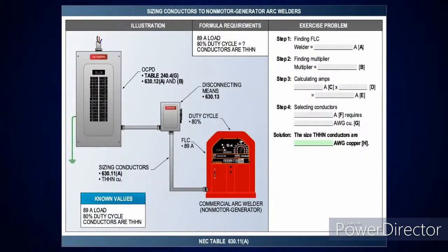Okay. And then you come over here. Here you have a commercial type arc welder. We've redrawn these too. And you're going to see we have an 89 amp load and an 80% duty cycle. Step one, you got your welder, it's 89 amps. Then all you need to do is look at table 630.11(A), pick up the 80% duty cycle, come across, get your multiplier, do your calculation, and size your conductors.